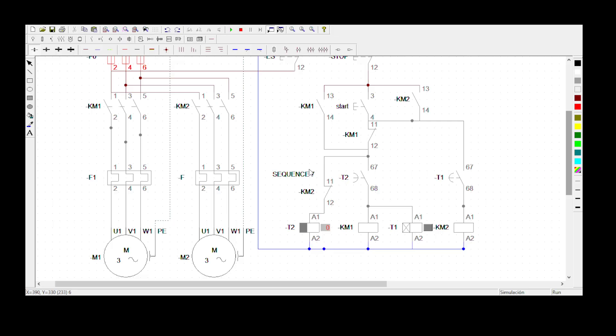Let me explain what's happening again. We want Motor 1 to start when you press the start button, but we want to be able to start Motor 2 using the same start button - however, Motor 2 must not start automatically. I added a KM1 normally closed contact so that immediately when KM1 energizes it becomes an open loop, preventing KM2 from energizing. After 10 seconds the normally open becomes a normally closed, but you don't want power to flow until you press the start button.